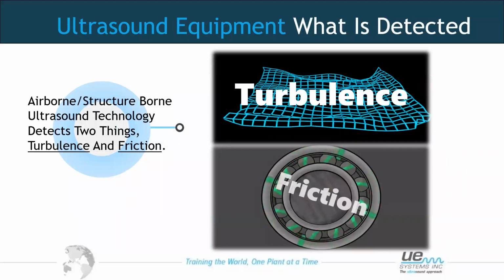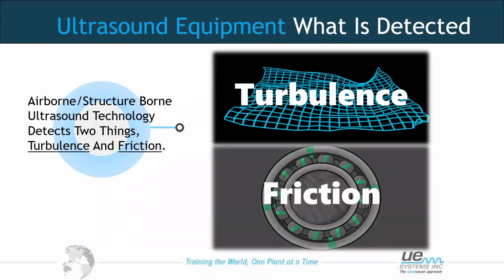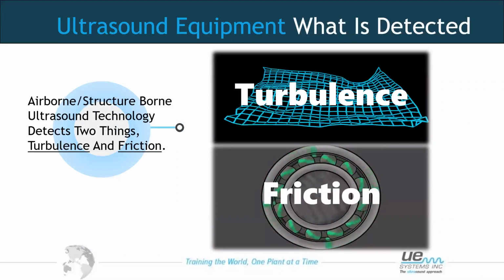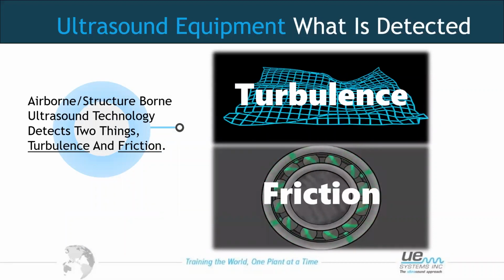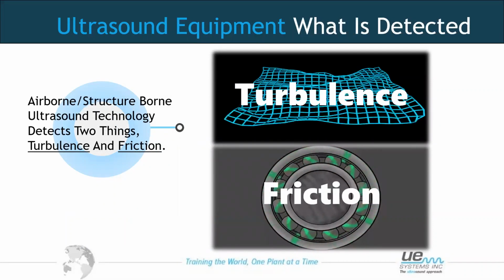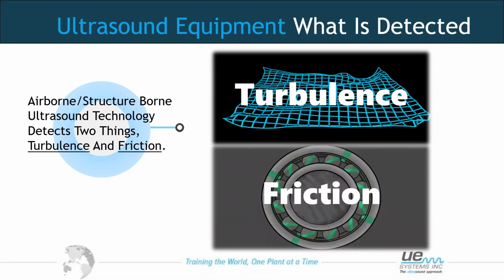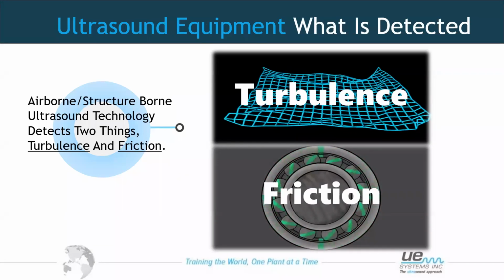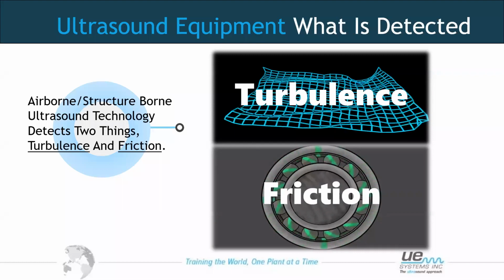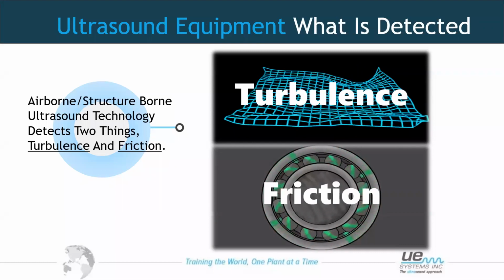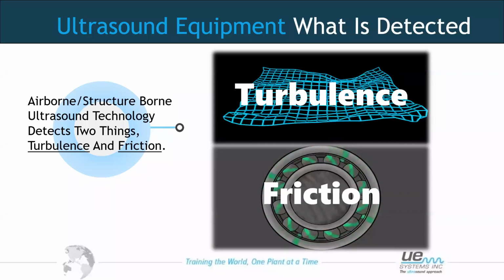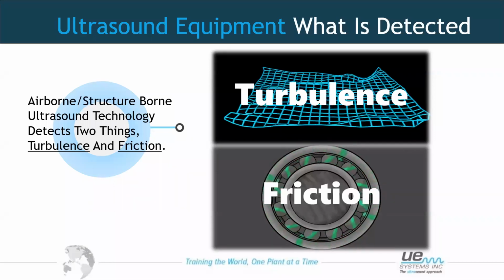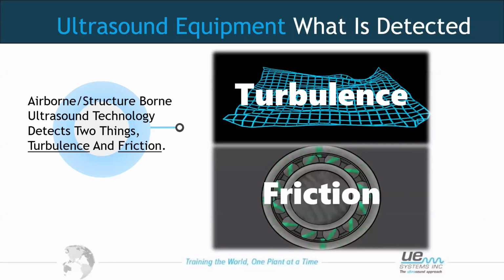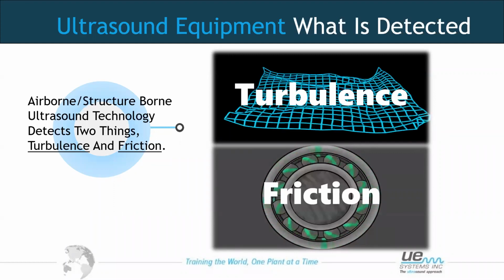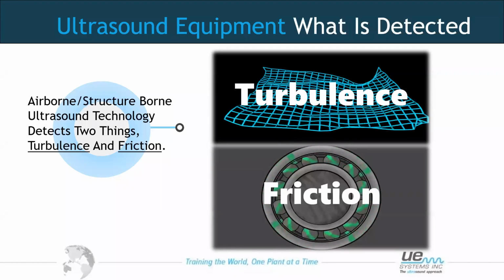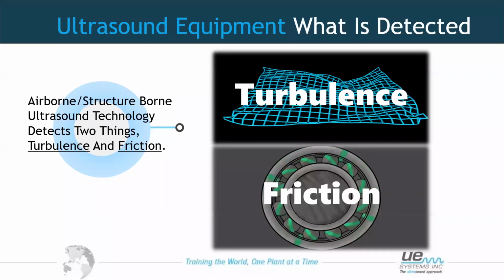There are two ways that ultrasound is generated. The first way is through turbulent flow. If we think about a pressurized system with a leak, we would gain turbulence from that, and that would generate ultrasound. In some cases, if it's strong enough, it will generate audible sound. Another way ultrasound is generated is through friction. Anything that's moving, rotating, rubbing together will also generate ultrasound, but that will be trapped within a solid structure. So we would use a contact approach to listen to the sound inside the asset.